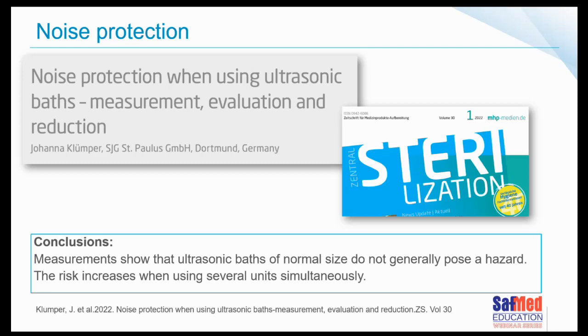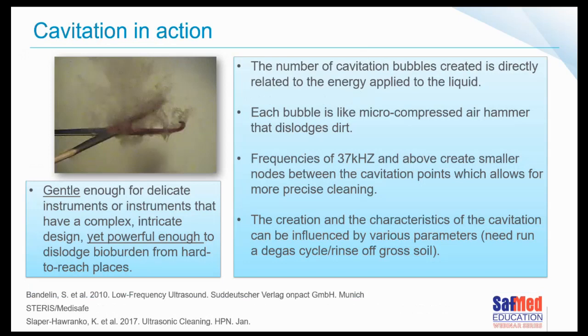But what they did find, thankfully, is that measurements show that ultrasonic baths of normal standard size do not generally pose a hazard. It's only that the risk will begin to increase if you're using several units simultaneously. So remember, if you're in a tight environment and you've got a huge amount of noise in a small place, then maybe you need to worry about protecting everybody's hearing. And under normal general circumstances, thankfully, our standard size baths are not hazardous. Again, look at the manual of your device and make sure that it's designed for healthcare and that it's safe, not over 85 decibels.